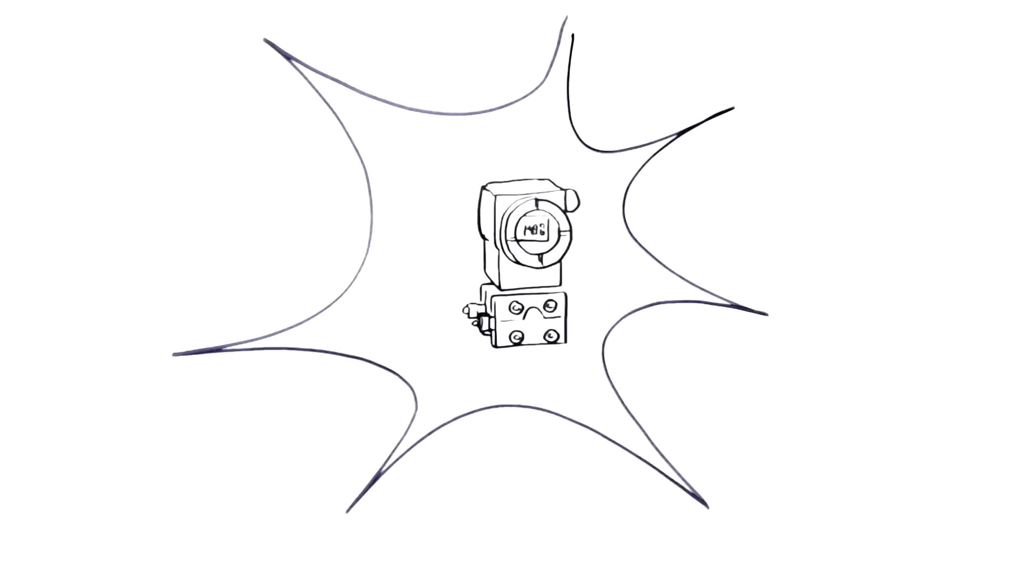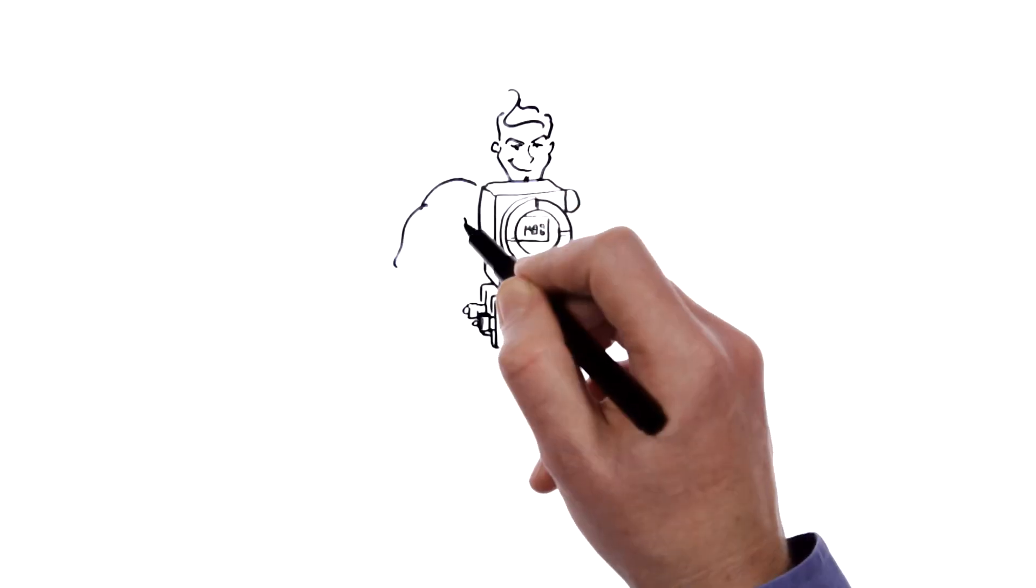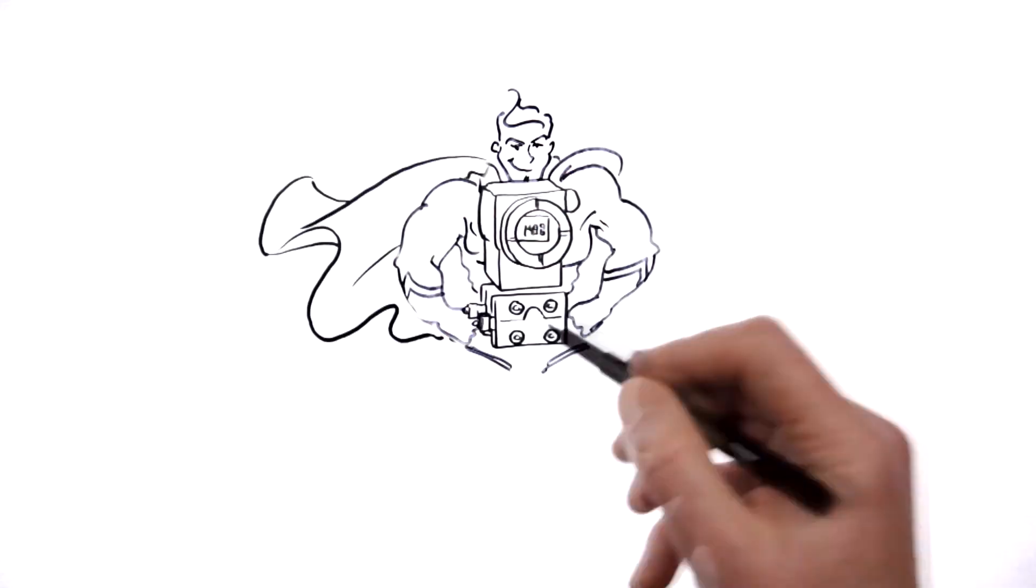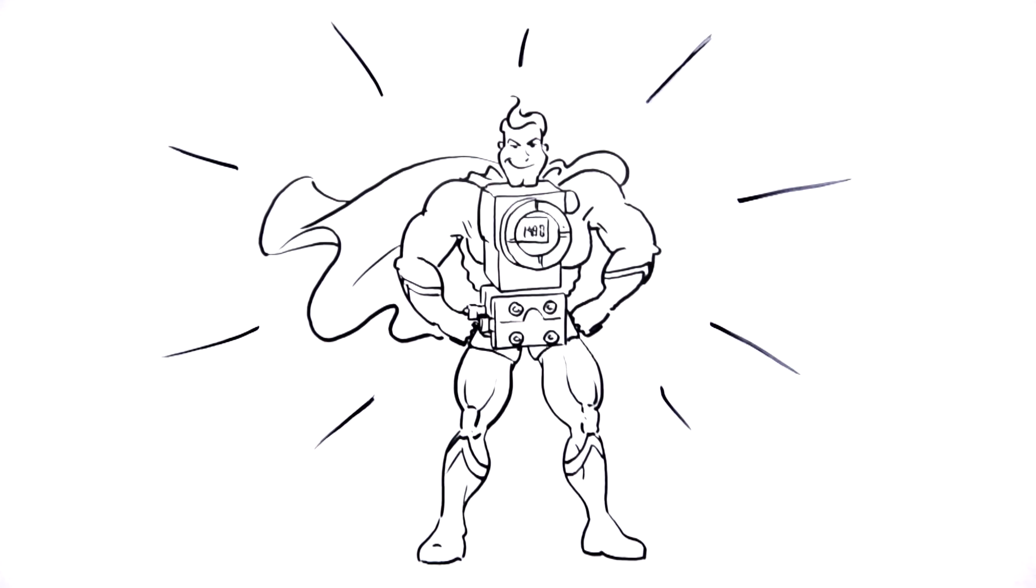And for the highest requirements, SITRANS P500. 0.03% linear characteristic accuracy. Total performance 0.09% with turndown 1 to 5. Response time below 88 milliseconds. A natural superhero.